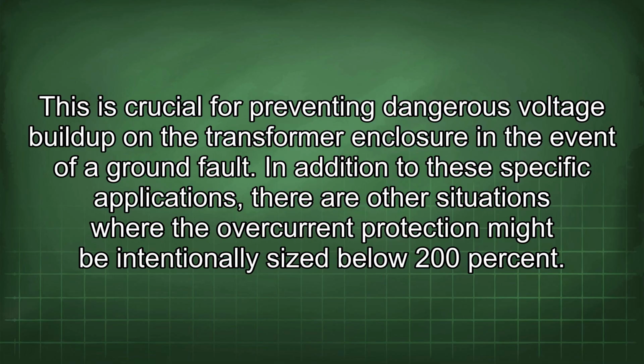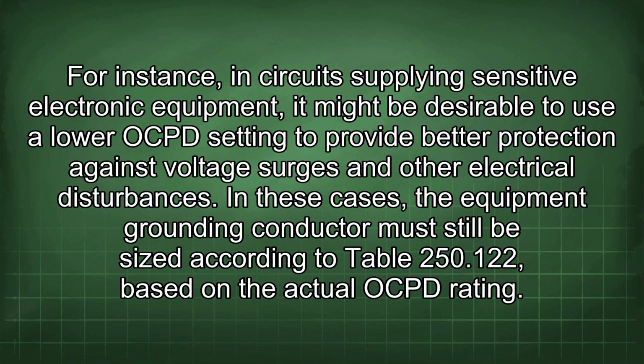In addition to these specific applications, there are other situations where the overcurrent protection might be intentionally sized below 200%. For instance, in circuits supplying sensitive electronic equipment, it might be desirable to use a lower OCPD setting to provide better protection against voltage surges and other electrical disturbances. In these cases, the equipment grounding conductor must still be sized according to Table 250.122 based on the actual OCPD rating.